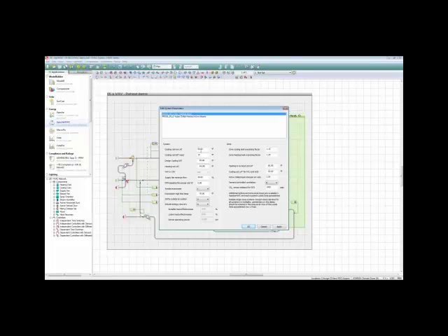So some new sizing tools in there. There's the supply fan minimum flow rate that I mentioned, which defaults to 20%, and that means that in the middle of the night, 3 in the morning, if the system comes on because one room needs some heat, this will force the system fan to run at 20% of its maximum flow rate, depending on what you put in here. Okay. The rest of this is all pretty nearly the same as it was before.